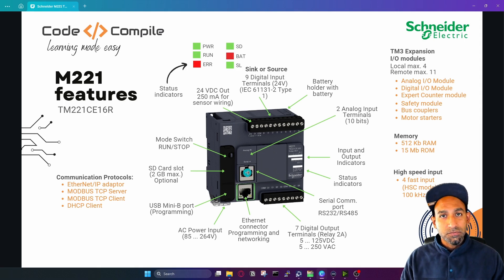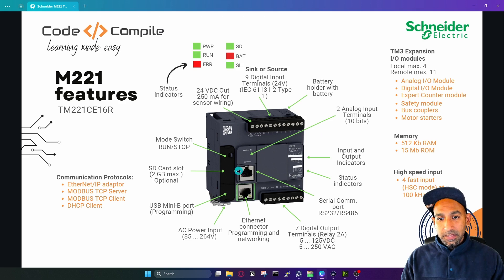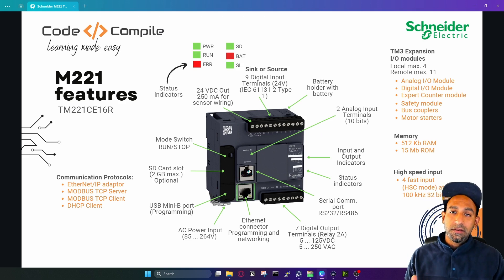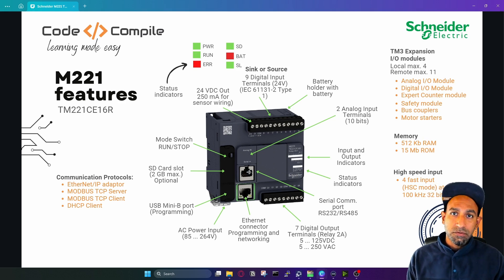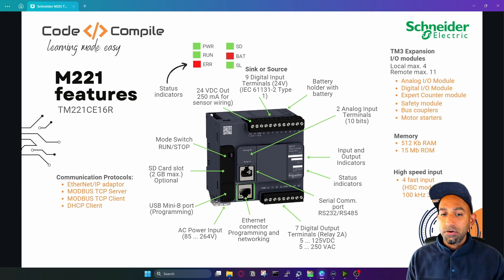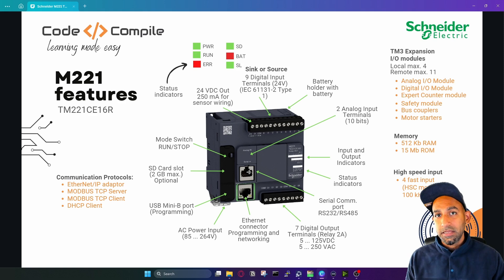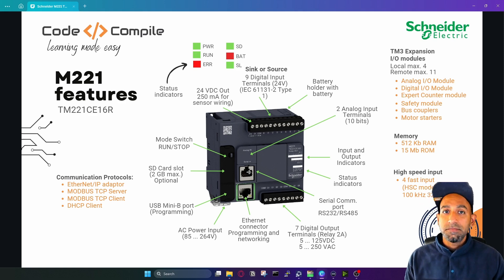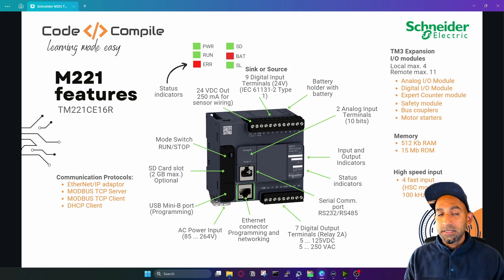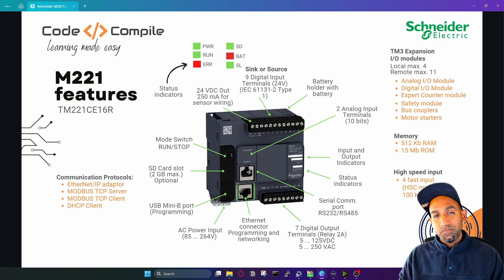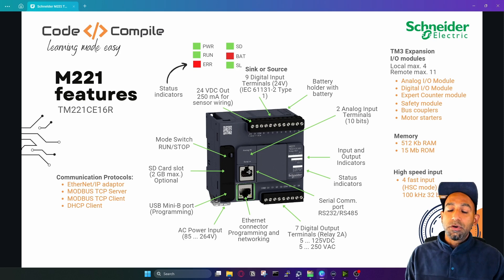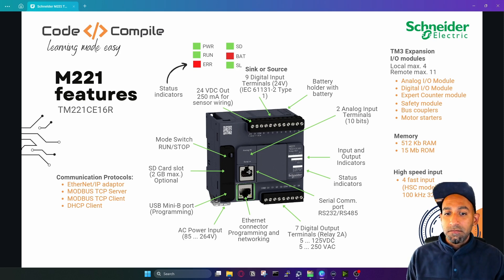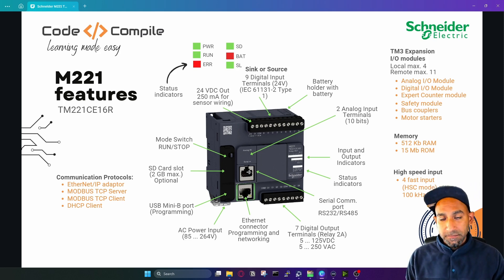You have a serial communication port — it's an RJ45 terminal. With the serial port you can connect to different devices via RS-232 and RS-485. So if you have an HMI, a remote terminal, or a power meter sending signals via Modbus, you can connect to this PLC and get readings. We are going to connect this terminal to our VFD and see examples of how to control a VFD via RS-485.